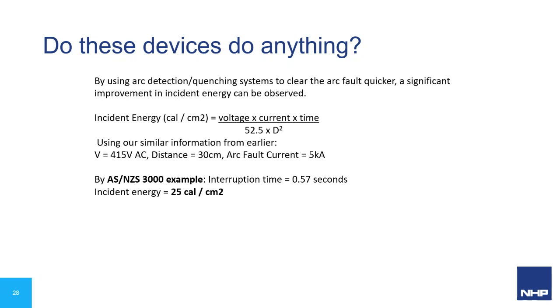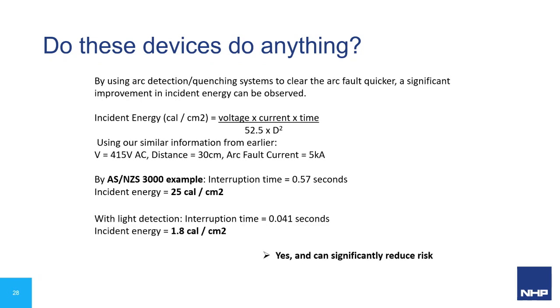So let's replace that with light detection. An example we've put together before is 0.041 seconds. That's 1 millisecond for the light detection and then 40 milliseconds for the ACB to open. That brings down the incident energy to 1.8 calories per centimeter squared. So that's pretty damning in terms of the numbers. Keep in mind the AS3000 example is a worst case scenario, but you can see that by reducing the amount of energy coming in, there can be improvements around PPE or exactly how you go about that. But also the amount of energy and cleanup and everything required for the board can significantly change.